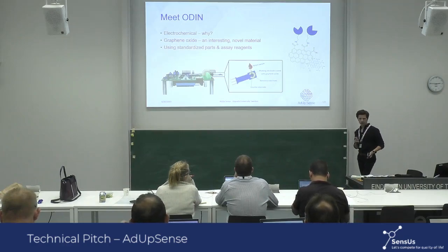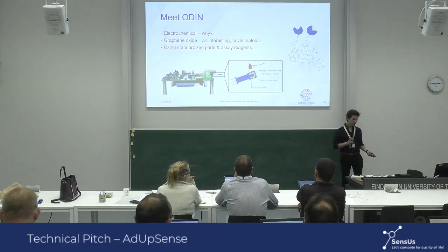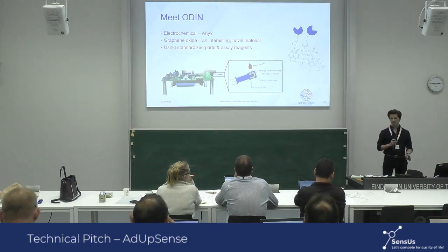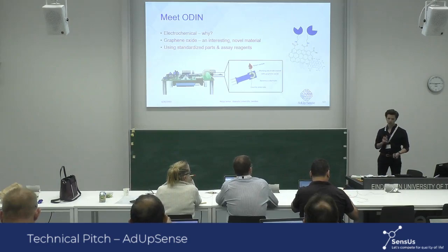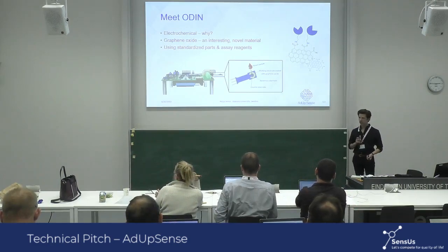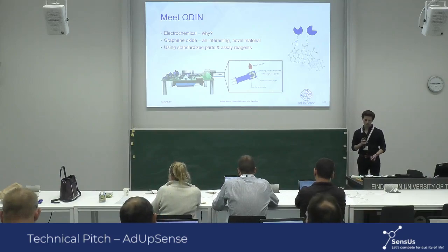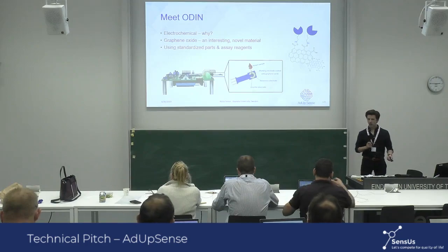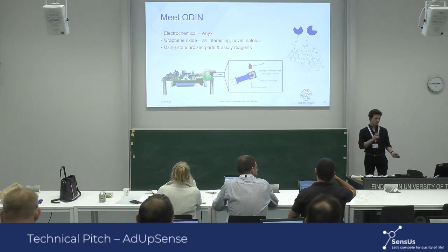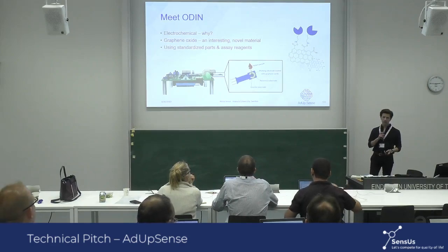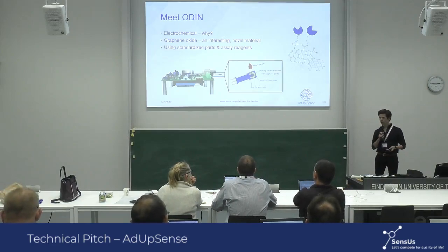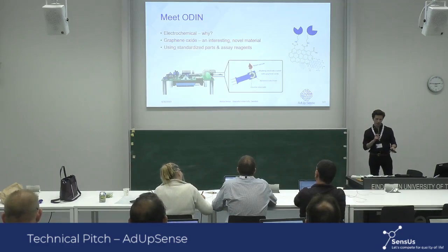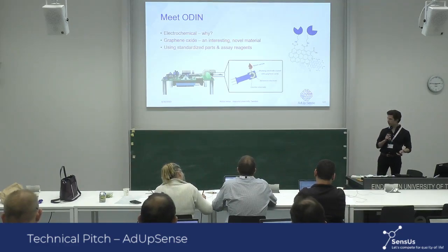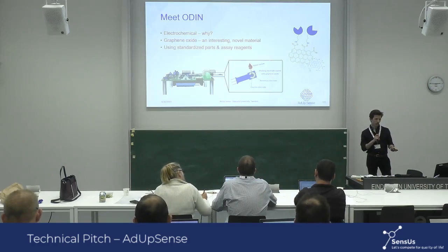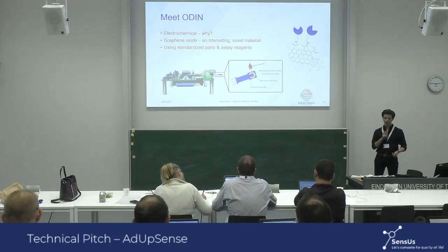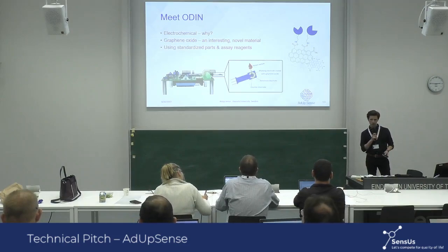We modified our electrodes with graphene oxide, a rather novel material, and this allowed us to covalently attach anti-adalimumab capture antibody through the use of very standardized EDC NHS chemistry and protocols. Now, with all of this, how would one perform a measurement? One would simply have to let only 4 microliters of a sample incubate at the electrode for around 15 minutes. The excess would then be washed off, and 50 microliters of a probe solution would be added. 30 seconds later, using differential pulse voltammetry, you have your result.